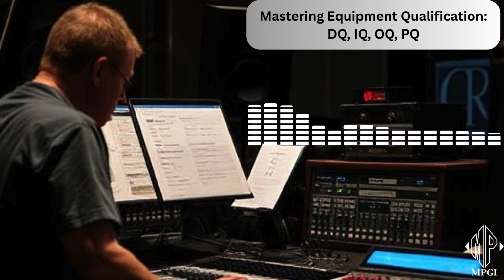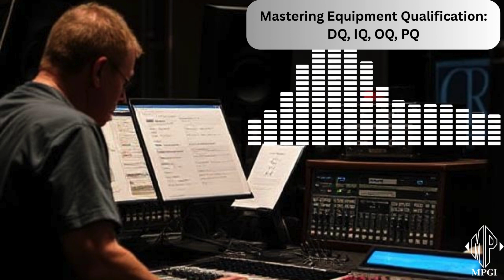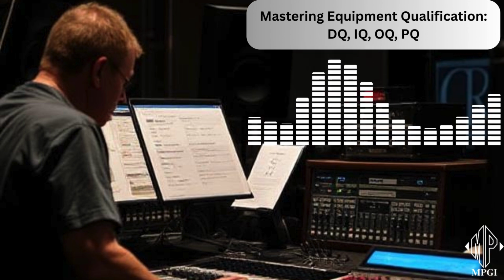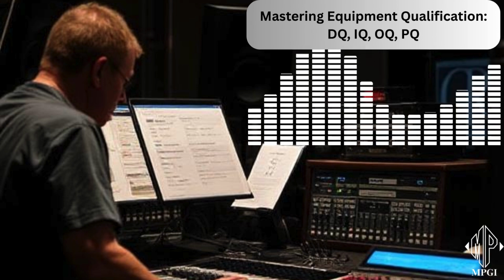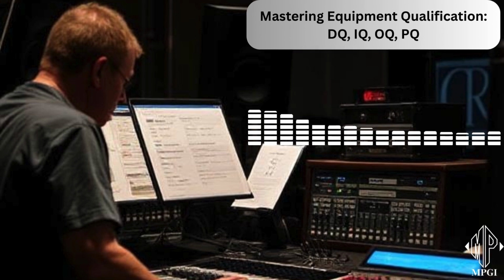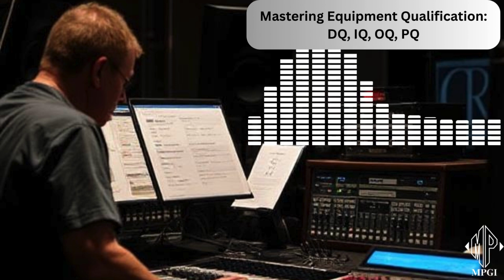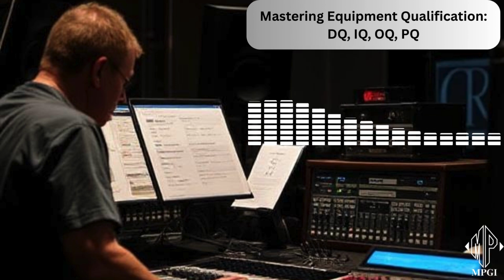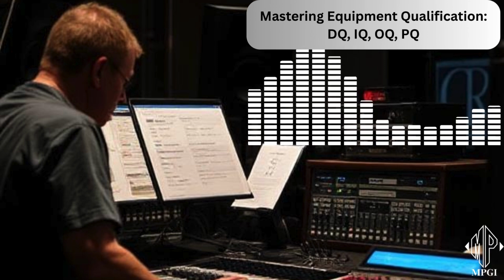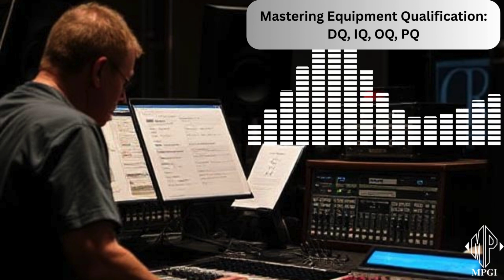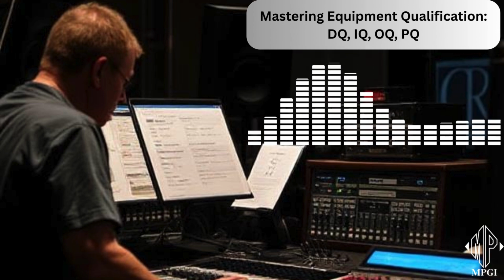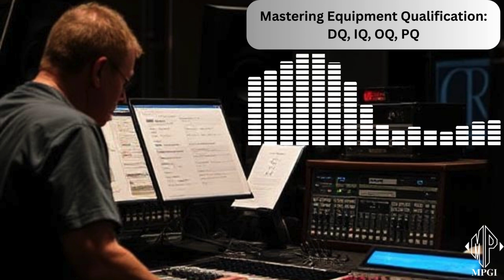Now, what about the documentation generated during OQ? You've got the OQ protocol, of course, laying out the test plan and acceptance criteria. Then you've got the detailed test plans and procedures for each test. So it's like a recipe book for the tests. Right. Then there are the test records and data, capturing all the results, and the calibration certificates for any instruments used during OQ. Again, ensuring everything is traceable and verifiable. Exactly. And like before, if there are any deviations, they go into deviation reports, along with how they were addressed. Transparency is key. Absolutely. And finally, you have the summary report, which gives an overview of the entire OQ process, the key findings, and the final conclusion on whether the equipment passed all the tests. So it's a thorough package of documentation that provides evidence that the equipment functions as intended. The equipment is designed well, installed correctly, and has passed its operational tests.